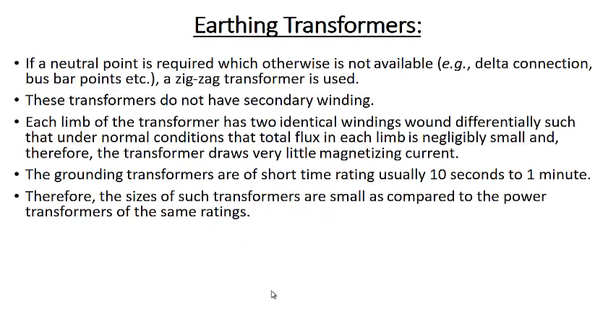Now we have one more thing, that is earthing transformers. This is used when the neutral point is required, which otherwise is not available, for example in delta connection or bus bar points, because their neutral point is not available. In that case, a zigzag transformer is used. These transformers do not have a secondary winding. They have only one winding.